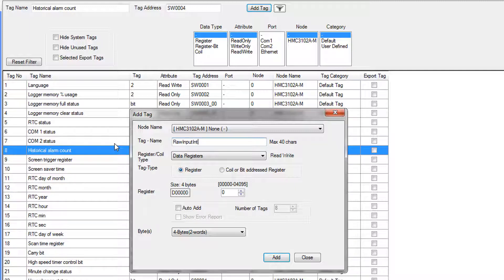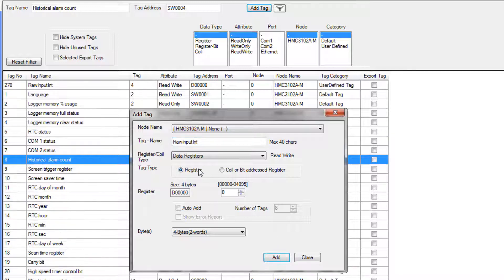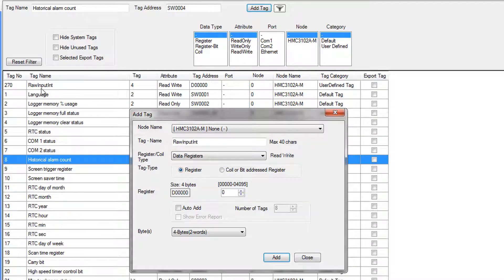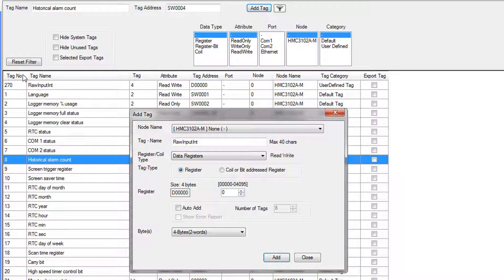RawInputInt. So RawInputInt is going to be a four byte tag at address D0. This is the tag that we are going to move the raw data from our analog input into. We click Add. And up here, the tag appears in the database. So the tag number, not super important. It's automatically assigned. You can't do anything with it.